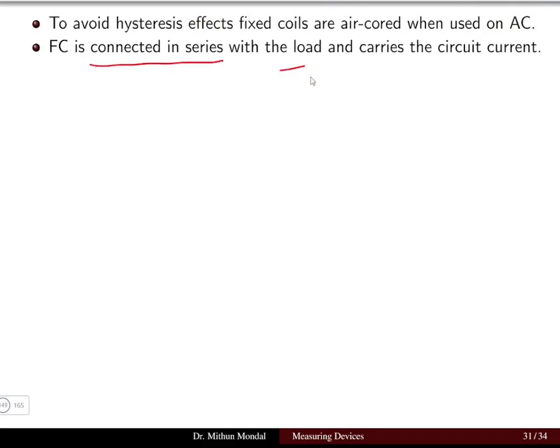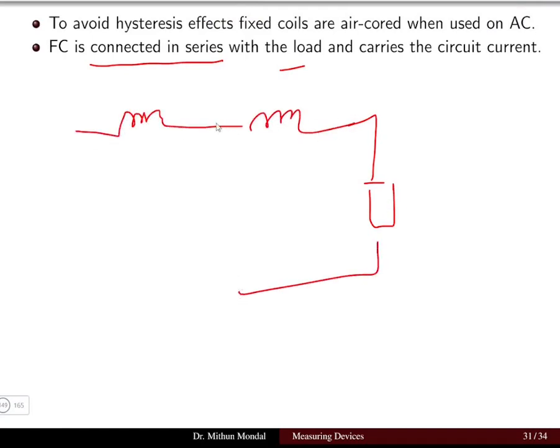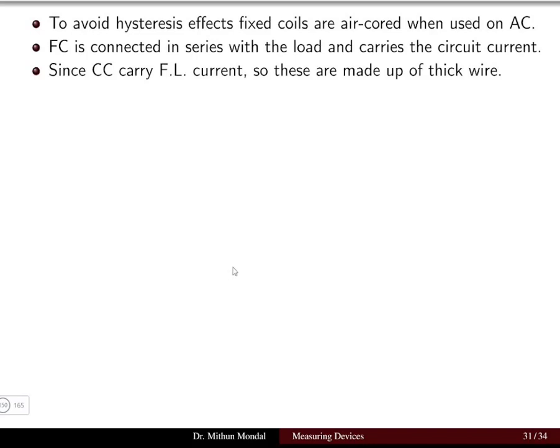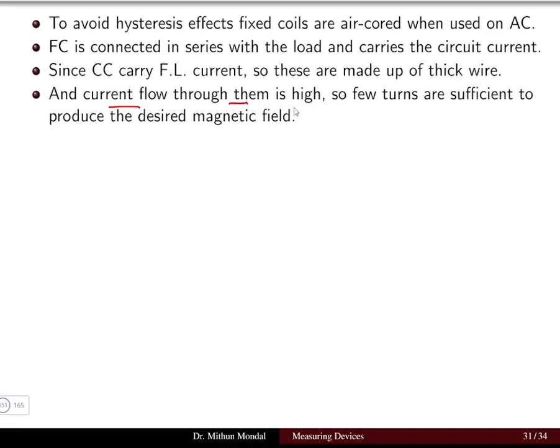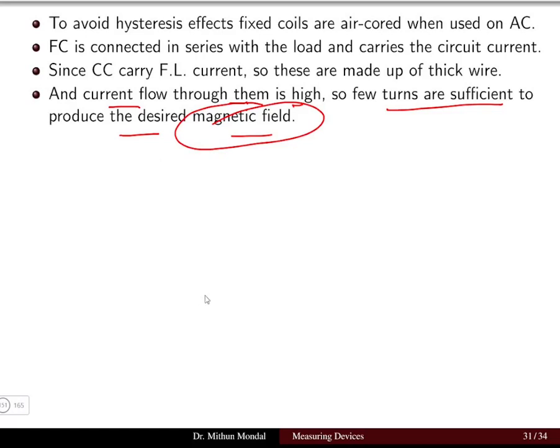The fixed coil is connected in series with the load and carries the total circuit current — the full load current. Because it carries such high current, the current coil must be made of thick wire, and only a few turns are sufficient to produce the desired magnetic field.